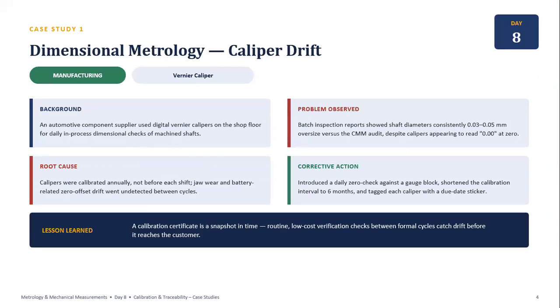So, case study 1. Our first case study concerns a digital vernier caliper used for dimensional inspection of machined shafts in an automotive component manufacturing environment. Although the calipers appeared to indicate 0 correctly, inspection reports showed shaft diameters consistently oversized by approximately 0.03 to 0.05 mm when compared with CMM inspection. The root cause was calibration performed only annually, while jaw wear and battery-related zero drift remained undetected.